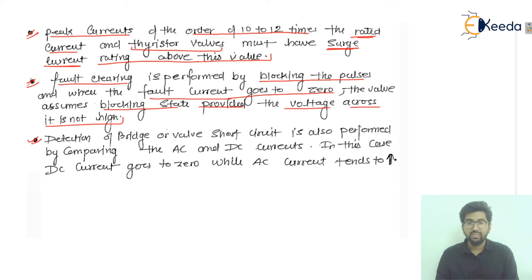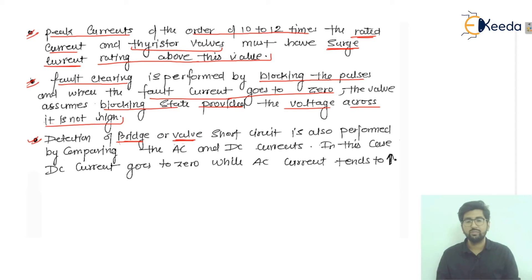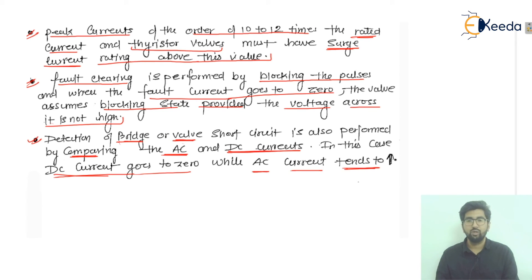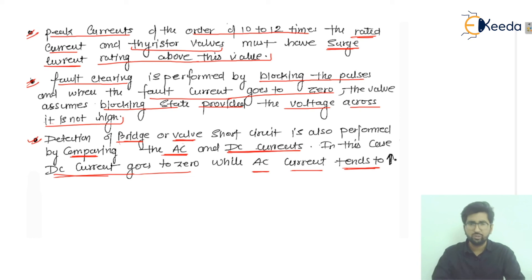Detection of a bridge or valve short circuit is performed by comparing the AC and DC currents. If there is a short circuit in the bridge or any of the valves, it is detected by comparing AC and DC currents. When this occurs, the DC current goes to zero while the AC current tends to increase. That is all about short circuit in a bridge.